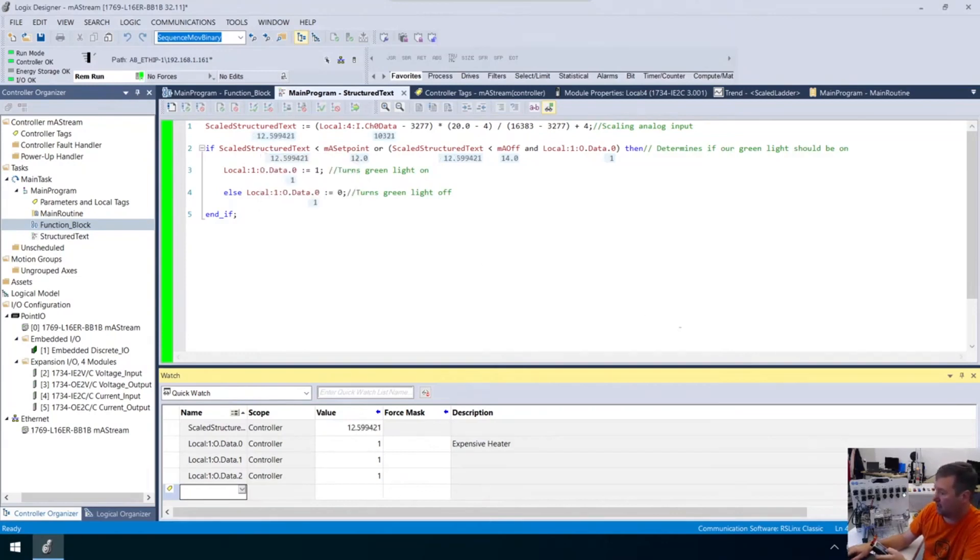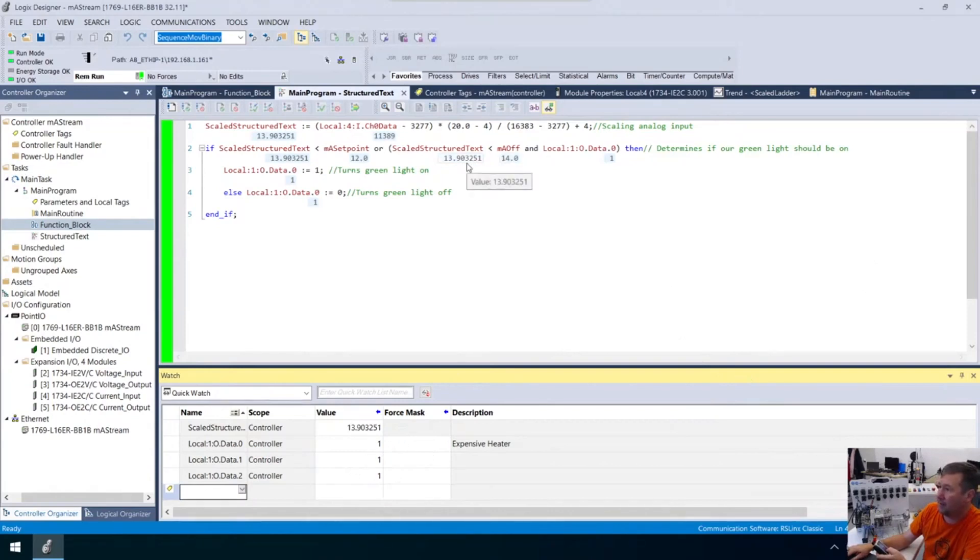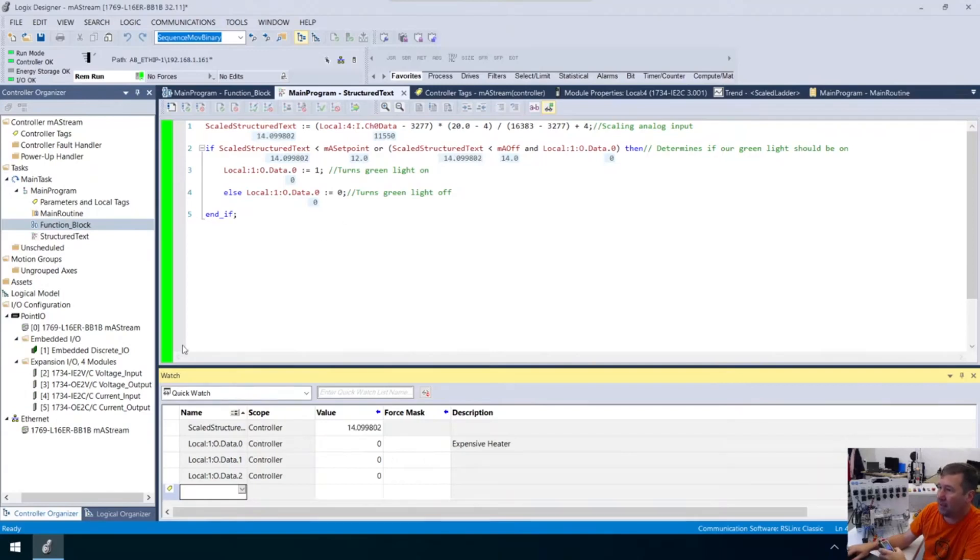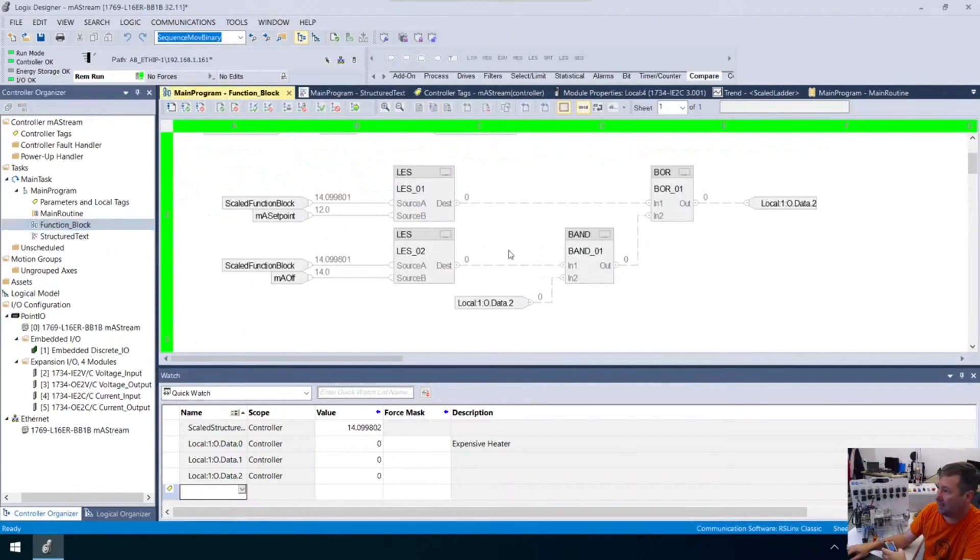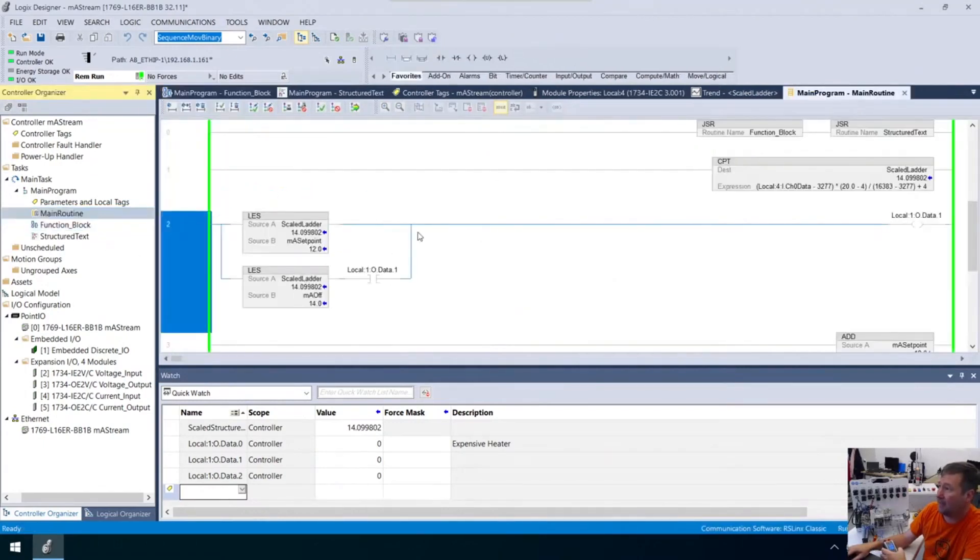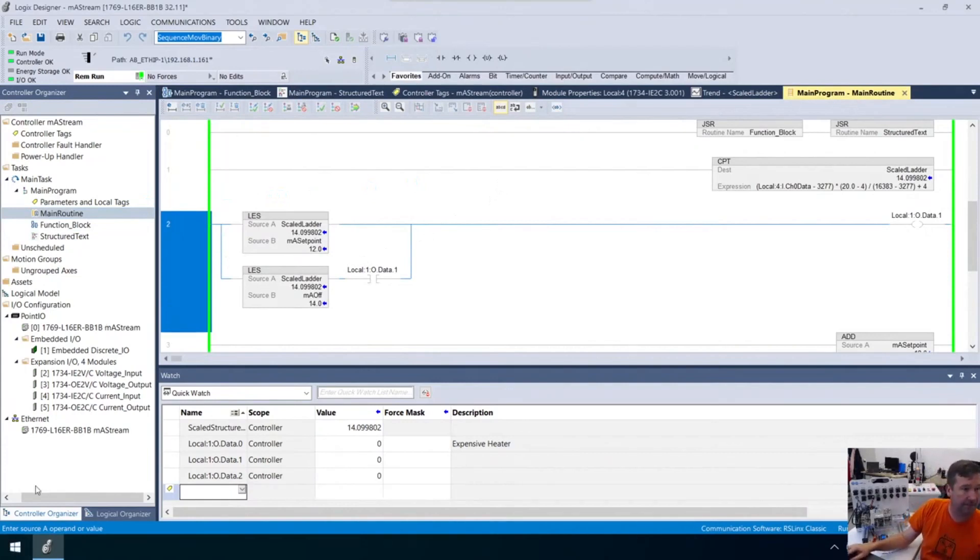But okay, let's go up to 14. Well, actually, I'm going to bring it to 13.9. And they're all ones. Now I'm going to bring it to 14.1. And we can see right here is what we're looking for. And that's going to go to zero. So this right here works exactly the same as this right here, which works exactly the same as this right here. So there are three ways that you can do this. I'll put a link to the 4 to 20 milliamp lesson series in the description. Till next time.